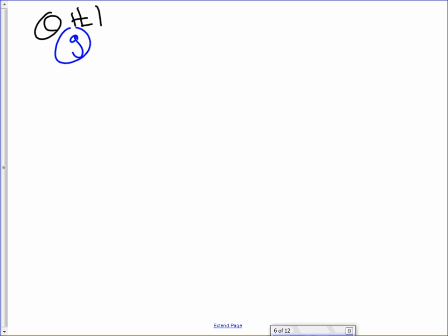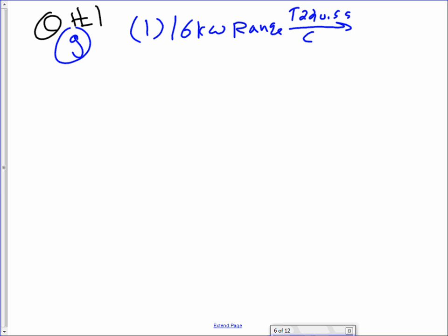So I have one 16 kW range. From the table 220.55 under C, would you guys come up with the demand for one range under C? 8 kW, right? One range under C, 8 kW. But this range, guys, is more than 12, so you need to up this number 5% for every kW. That range is more than 12.